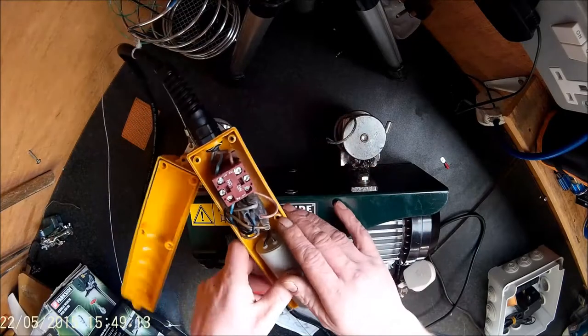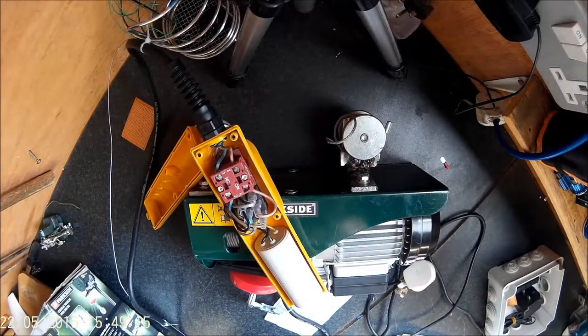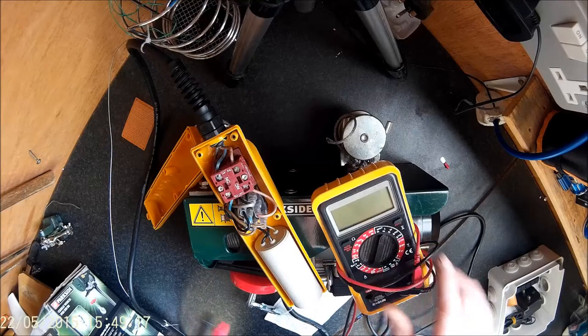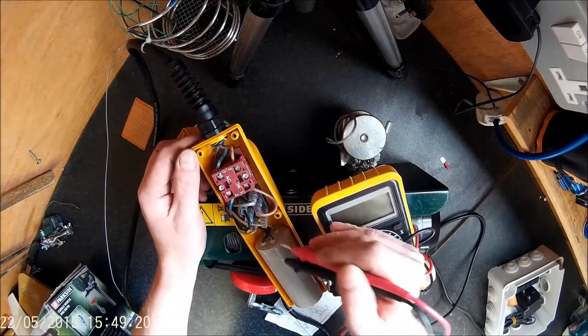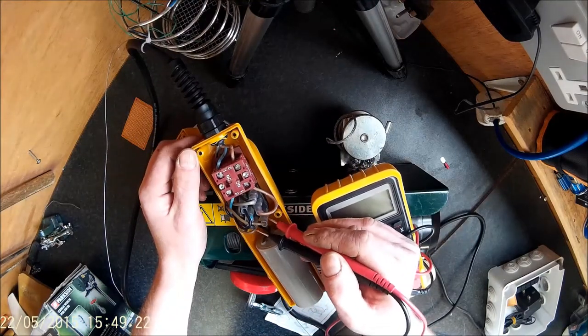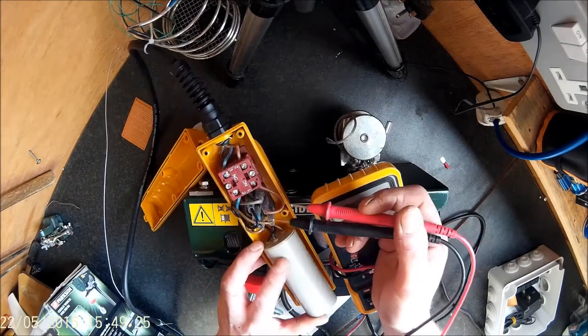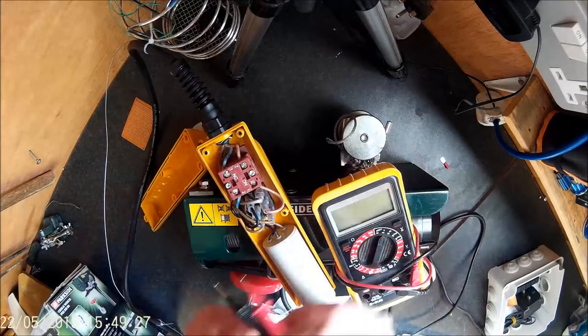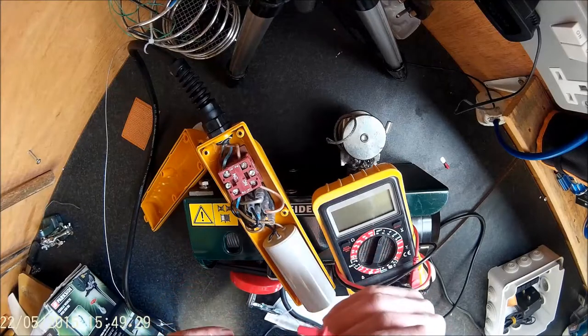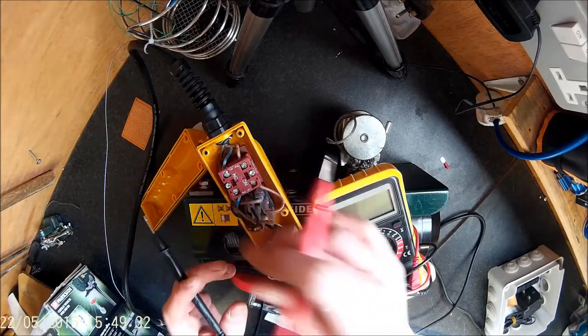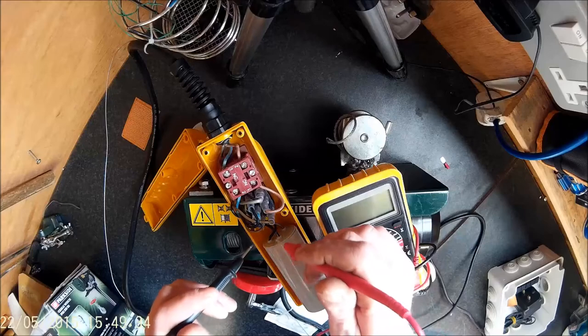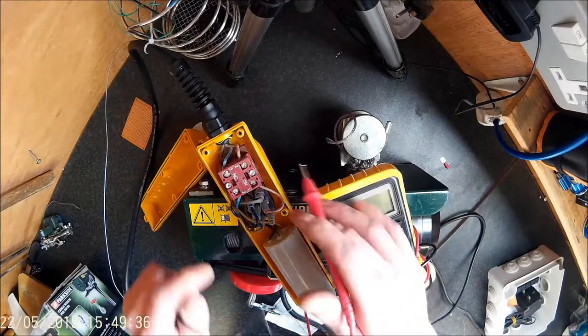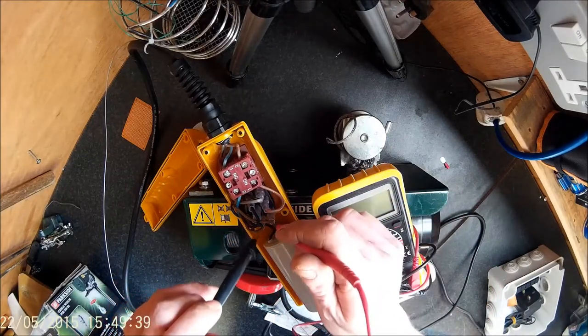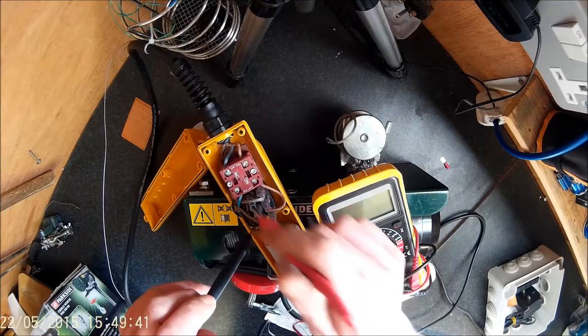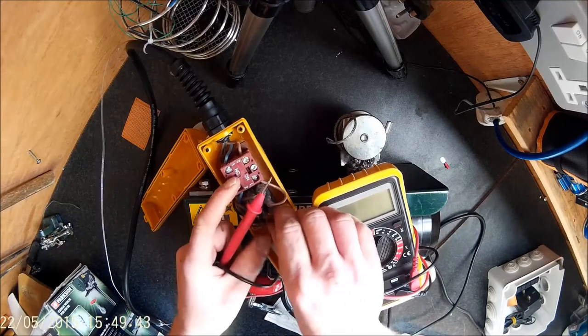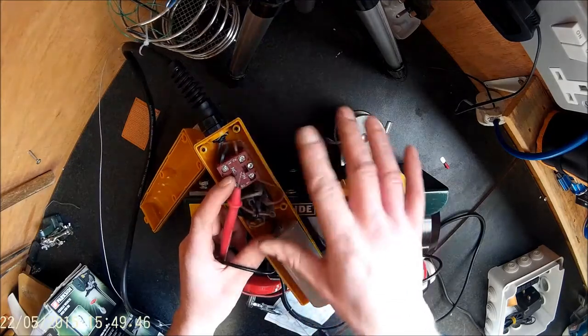So the first thing I'm going to do is get my multi-tester. Because there's a capacitor connected to these terminals, and a capacitor acts like a large battery, it holds energy to start the motor. I want to discharge it. I don't want to take this apart and start messing about and tap into it and then get a shock. So you'll get your multi-tester or a light LED, anything, and just discharge it. Hold the two terminals of the capacitor, discharge it, spin these off and tap into them.